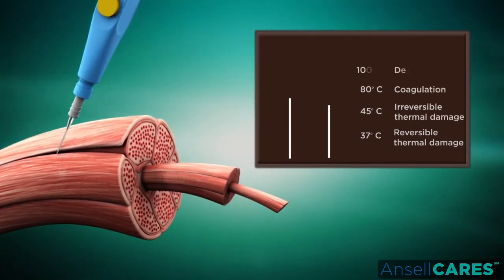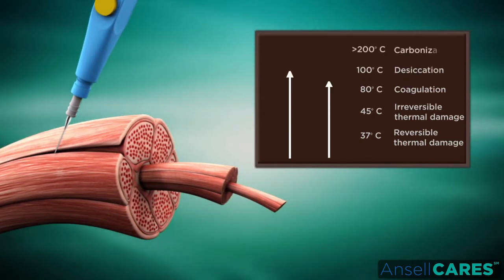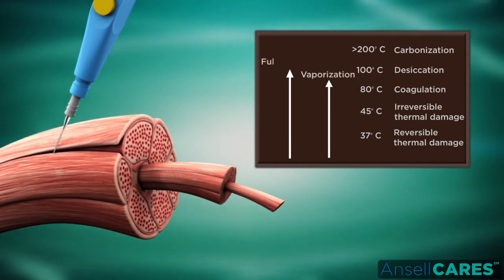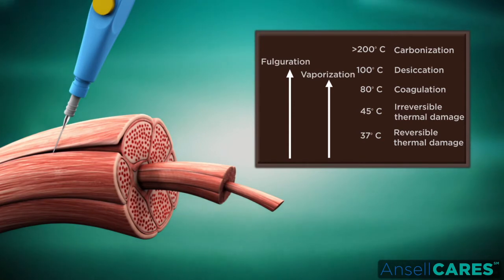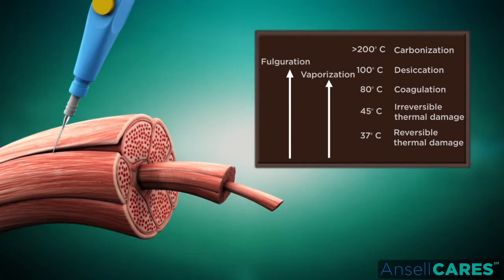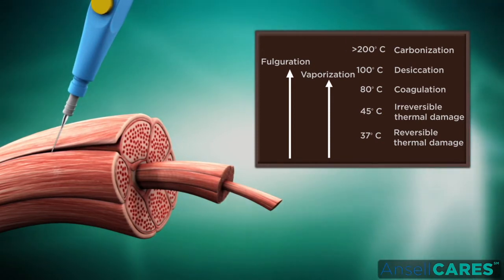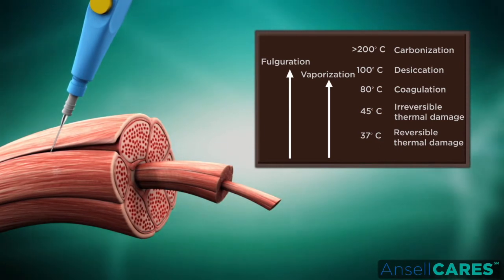Once tissue temperature exceeds 45 degrees Celsius, the proteins in the tissue become denatured, losing their structural integrity. Above 90 degrees Celsius, the liquid in the tissue evaporates, resulting in desiccation or vaporization depending on how the heat is transferred. At 200 degrees Celsius, the remaining solid components of the tissue are reduced to carbon.